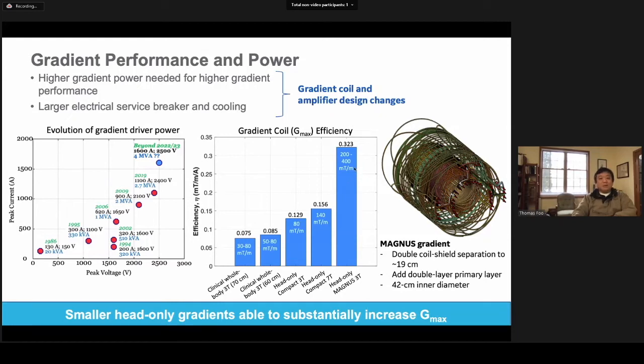And with a 2 MVA driver, it can go up to 200 to 300 millitesla per meter. And it can even go higher if you have a higher powered gradient driver available. The way it's achieved here is that we doubled the coil shield separation to 19 centimeters, added a double layer primary, and used a small diameter for the gradient coil. All of this leads to the ability to increase Gmax without substantially increasing the power. We cannot increase the power to the gradient driver without bound, because increasing power requires a larger electrical service breaker and cooling.